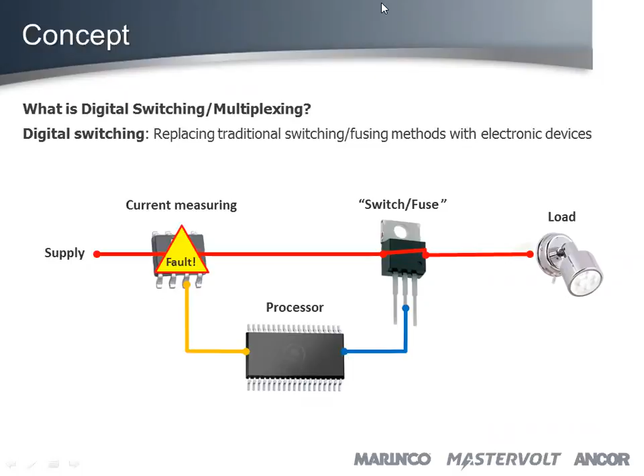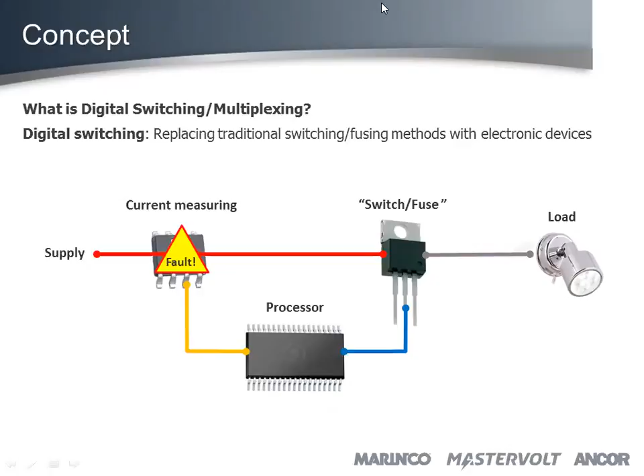That's how it works. The cool thing is the microprocessor can be told at what current it needs to trip. Our devices are limited to 10 amp or 20 amp max, but I can set that anywhere from 0 to 20 amps. So if I have an existing circuit set for 5 amps to trip, and I'm upgrading it with more lights, I can set it to 6, 7, or 8 amps. That's the flexibility customers get.